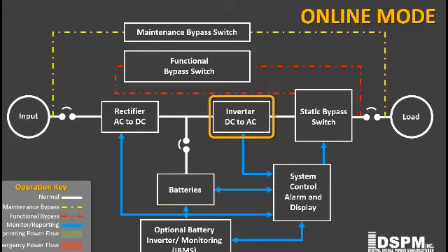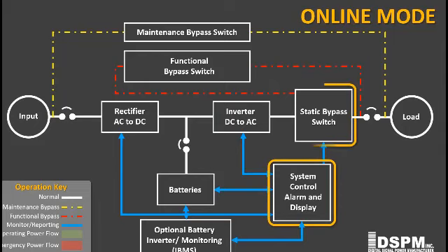The next step is delivery of the rectified DC current to the inverter stage that converts the direct current into pure, clean, alternating current delivered to your load. As you move through the inverter systems, we see DSPM system control and alarm display. This digital computer-driven technology monitors every aspect of a DSPM inverter and swiftly determines when and if power needs to be switched to the backup batteries by way of the digital static bypass switch. Or in the event of an inverter system failure, the static bypass switch will take the inverter offline and revert to your utility company's electrical feed. In all possible cases, DSPM's monitor keeps you informed in real time of the status of the system by way of an intuitive digital display.